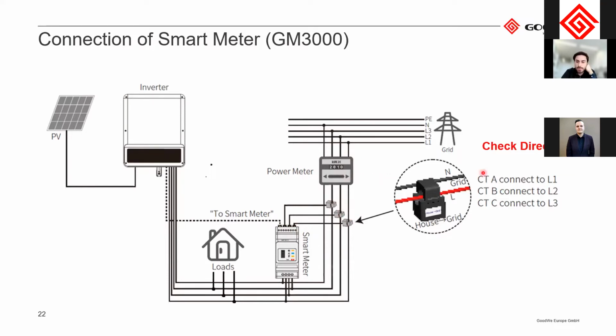And it's important here to check the direction of the CTs. I will show that later as well. They are marked with house arrow grid, or also if I look here, it also says house, or it says K to L, and K is house in this case, and L is grid. So make sure that it always points towards the grid.